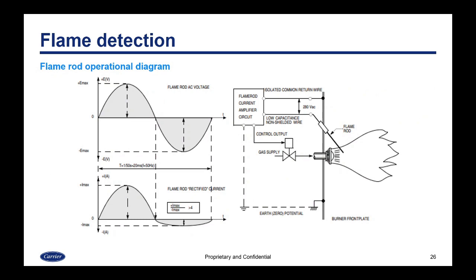Here's an operational diagram for the flame rod. In the image on the left, you can see the normal AC sine wave at the top and how the peaks are equally distant. At the bottom you can see the rectified current — the peak on one half of the AC cycle is about four times higher than the other, and that is how it can differentiate between a short and an actual flame signal. The image on the right shows the circuit and how it manifests into actually detecting the flame, showing the flame rod protruding into the flame itself.